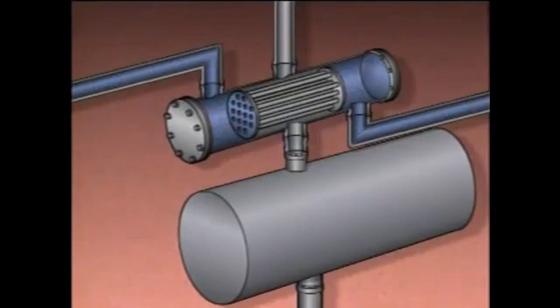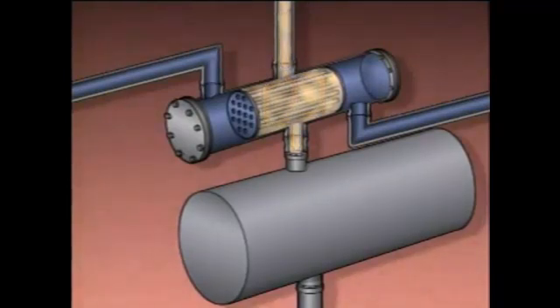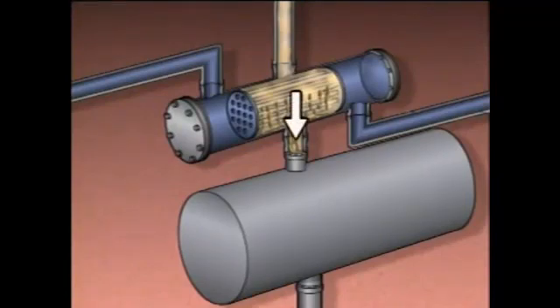On the shell side of the condenser, vapor passes through the inlet and flows around the tubes. When the vapor comes into contact with the cool surfaces of the tubes, heat is transferred from the vapor through the walls of the tubes to the cooling water. As heat is transferred to the cooling water, the vapor cools and condenses on the surfaces of the tubes. The condensed vapor, or distillate, drips off the tubes and falls to the bottom of the shell.